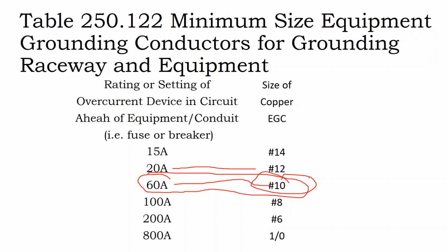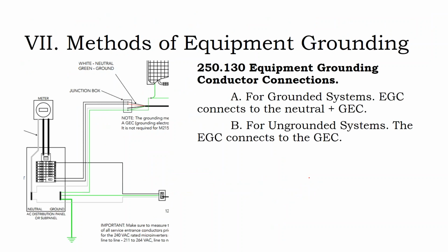So are you allowed to use that number 10 as an equipment ground conductor? Technically, no. It's smaller than number 4, and if it's an insulated cable being used as your equipment ground that's smaller than number 4, then it needs to be in a green jacket. If it were number 4 or larger, you could just buy some green tape and tape it off, but you could fail inspection because of that. No big deal. Some solar inverters may be ungrounded, and the big thing is they just don't have a neutral.